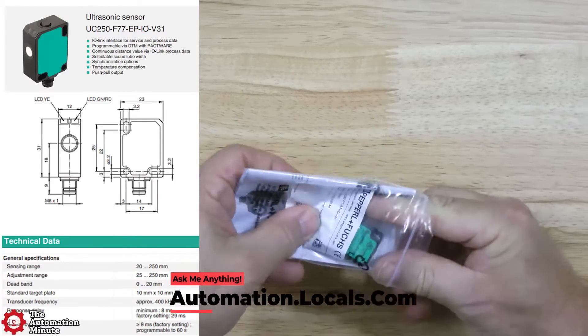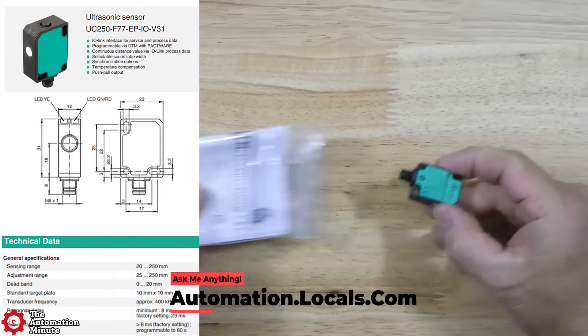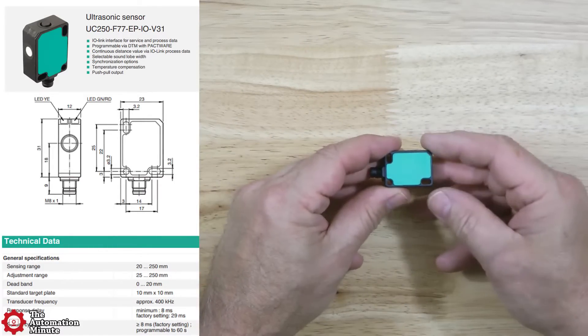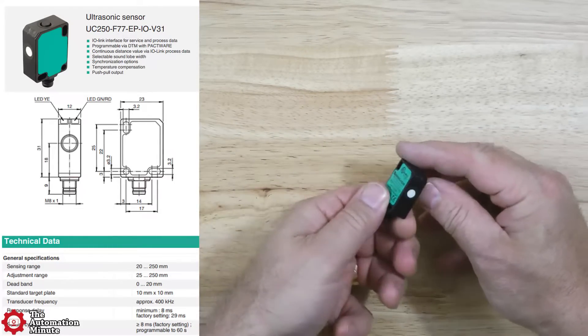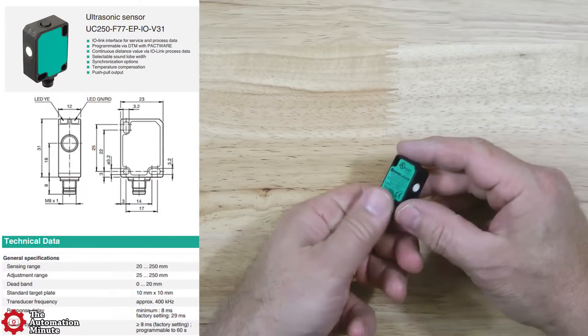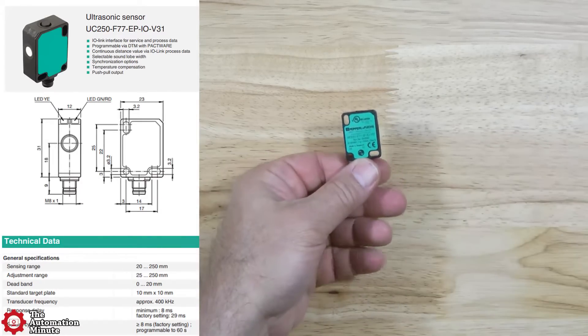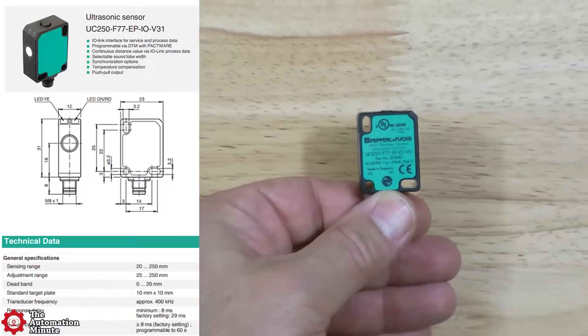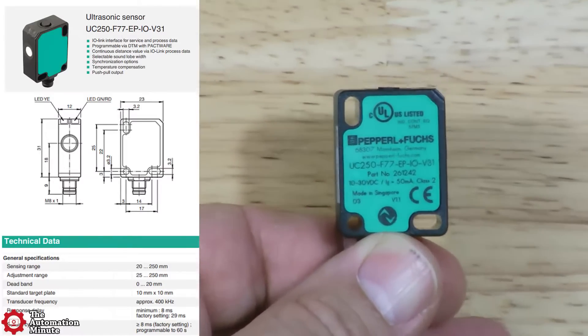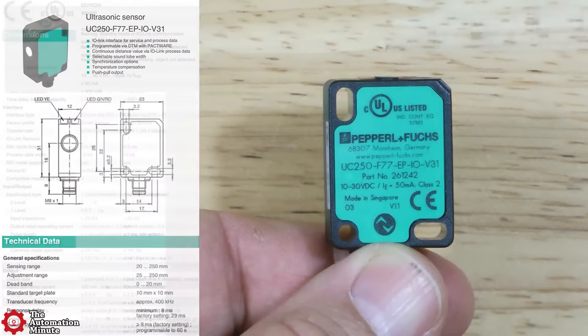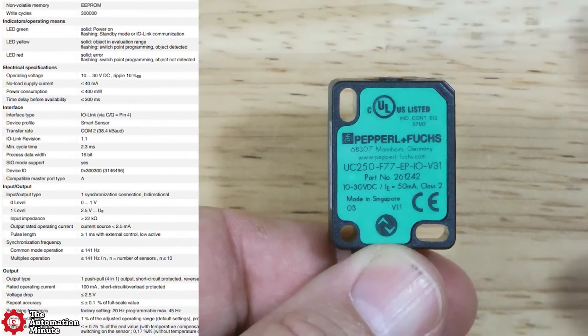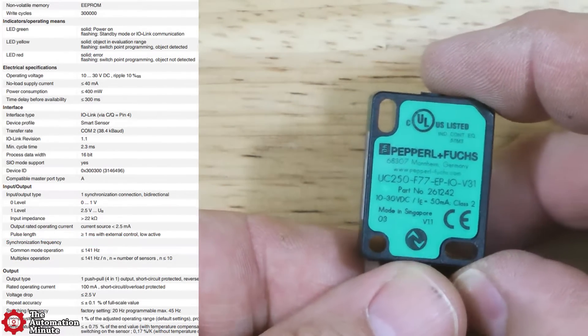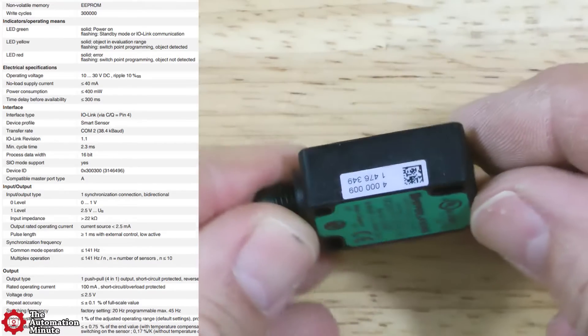It has an adjustable sensing range of 25 to 250 millimeters, and a cycle time between 8 milliseconds and 60 seconds, with a minimum response delay time of 8 milliseconds. Its operating voltage range is from 10 to 30 volts DC.